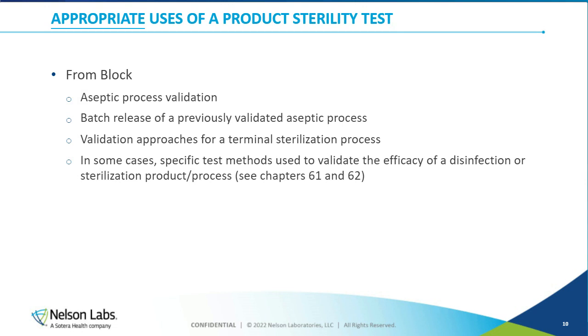A lot of monitors are being performed during that process with regards to environment and those few people that do have some interaction with the product during the process. Those are the types of aseptic processes where the problem is the product sterility test is being performed in as good, or in some cases in not as good a situation, just because you cannot always recreate a closed system in an isolator for some types of products. So what benefit would there be to a product sterility test? There is no benefit. So that's the kind of scenario we're talking about there.